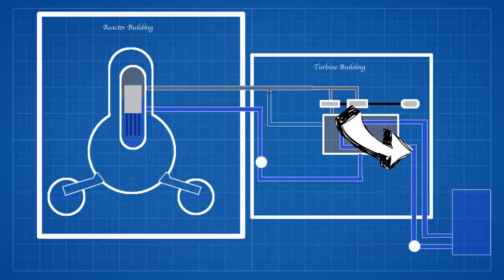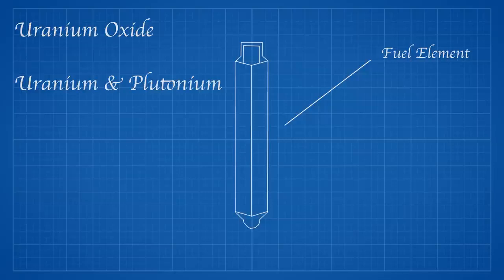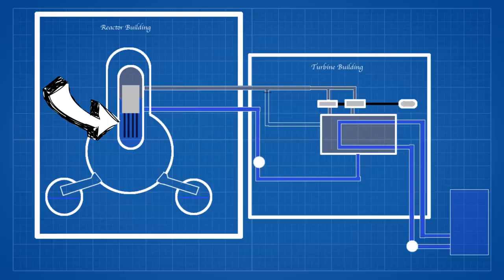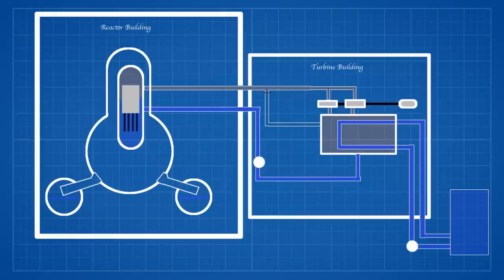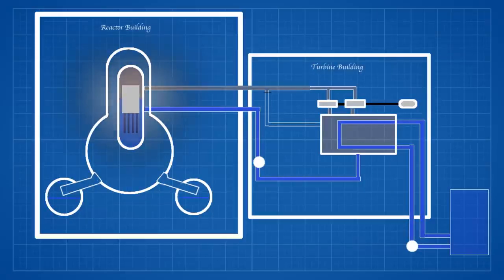The fuel used at Fukushima consisted of fuel pins bundled in square arrays. The fuel pins consist of low enrichment uranium oxide or mixed uranium and plutonium oxide fuel pellets enclosed and sealed in zirconium alloy cladding tubes. Each of the reactors had control rods for regulating the power and had 97, 137 and 185 across the three different BWR types. The rods were inserted into the reactor from underneath. The control rods had the ability to scram the reactors shutting down fission in an event of an emergency.